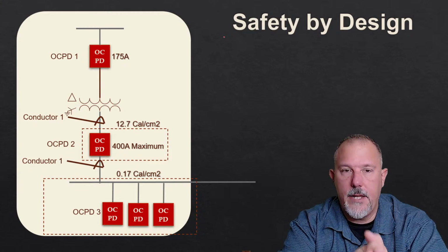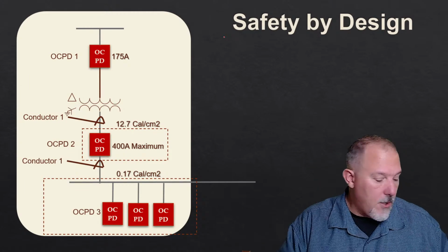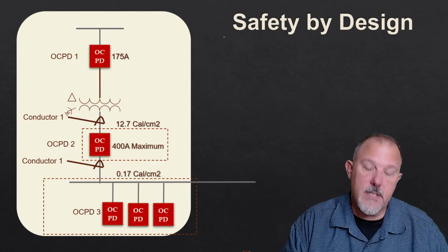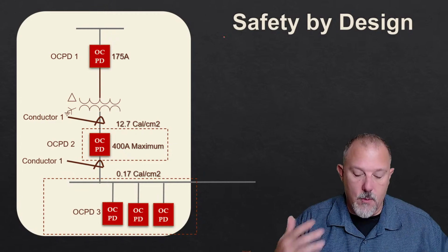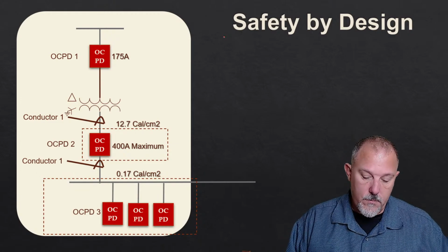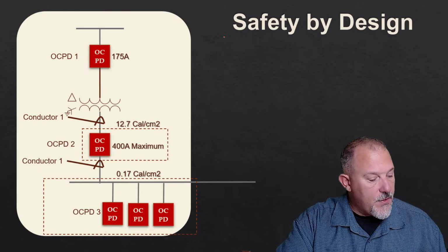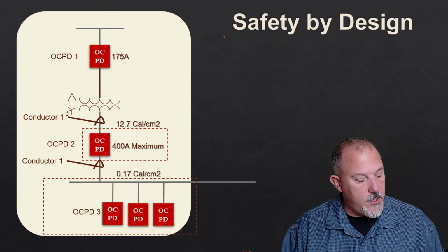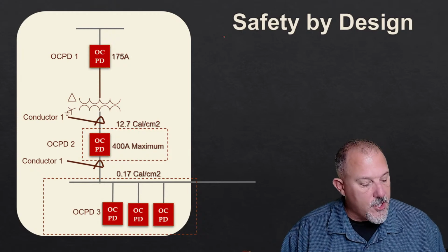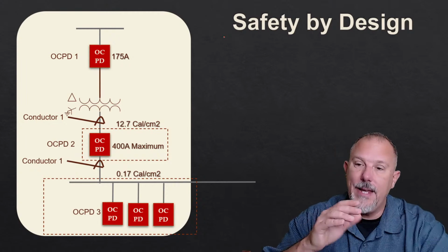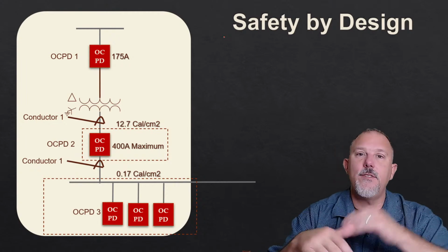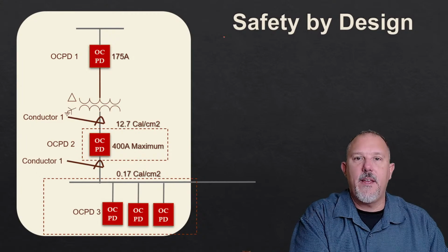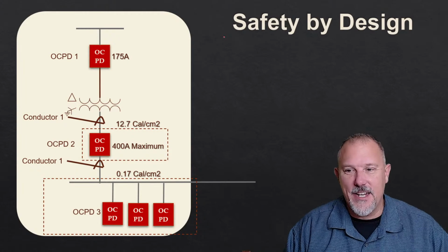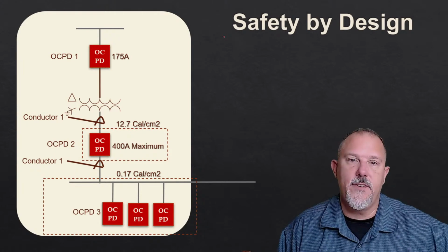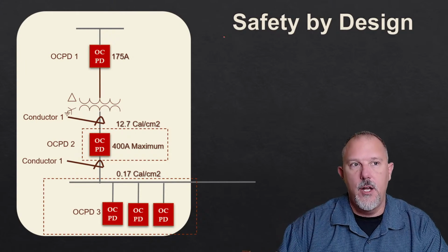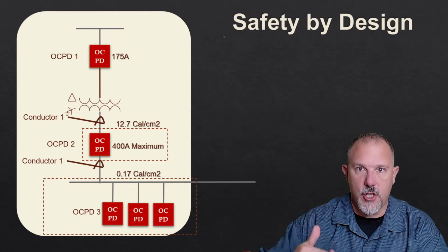I think it's related, and the reason I say that is that what he's referring to are the barrier requirement, or the 6 disconnect rule, where we now have requirements that tell us, in 230.71, maximum limit 2 to 6 disconnects, that you have separate enclosures with the main service overcurrent protective device in each enclosure. So it's very similar. And here's what happens. Why did we make this change? We made the change in 230.71 because we were made aware of a hazard when we required the barriers on the service overcurrent devices.